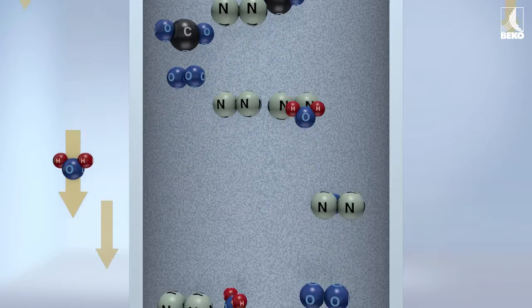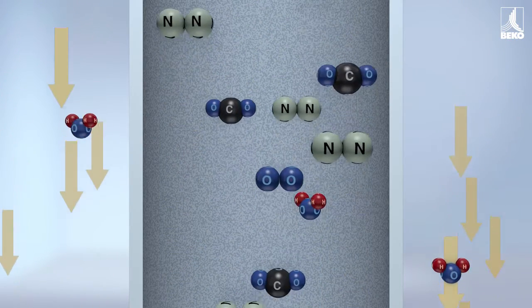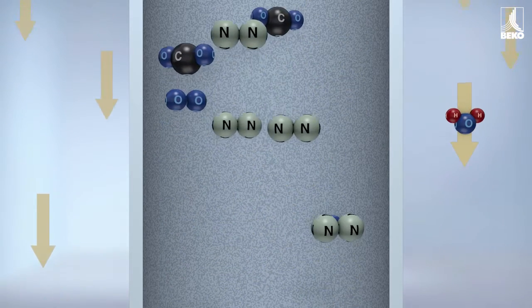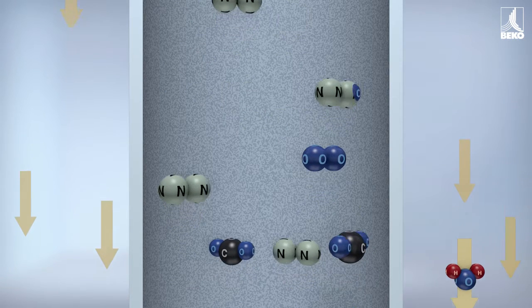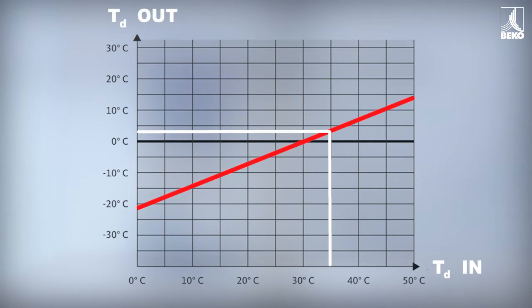As a result, neither oxygen nor any other elements are removed from the compressed air. This means the quality of the compressed air remains unchanged until drying is complete. This process is therefore also suitable for breathing air applications. The pressure dew point is consistently lowered regardless of its starting value.